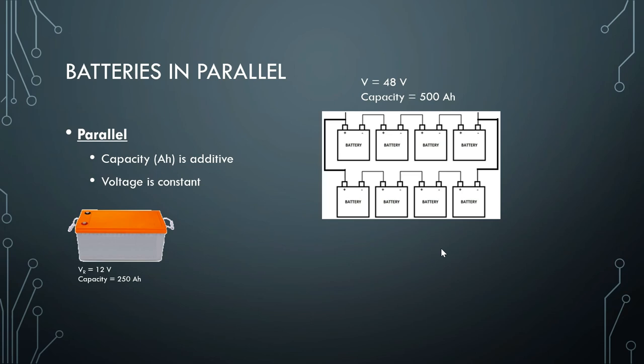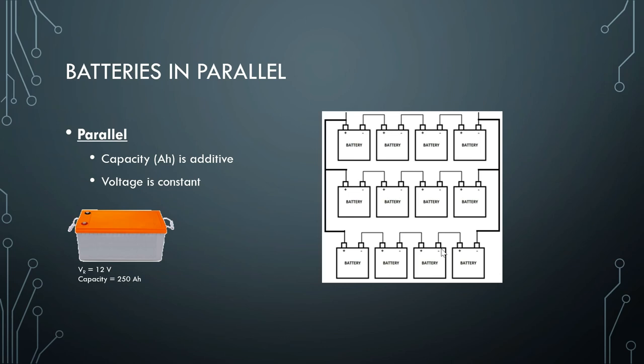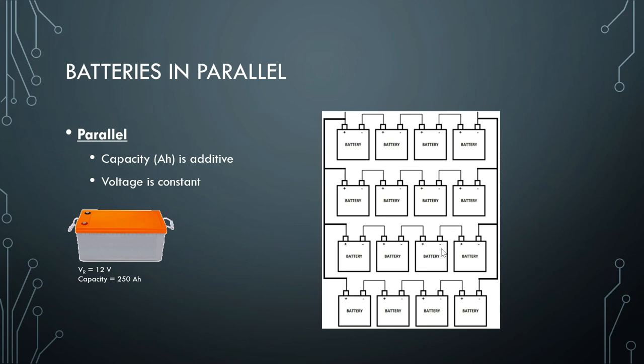If we add another string of batteries in parallel, that gives us the same voltage output of 48 volts and a capacity of 750 ampere hours. And if we connect yet another string in parallel, we still get 48 volts, and the capacity increases by another 250 ampere hours, giving this whole configuration a total capacity of 1000 ampere hours.